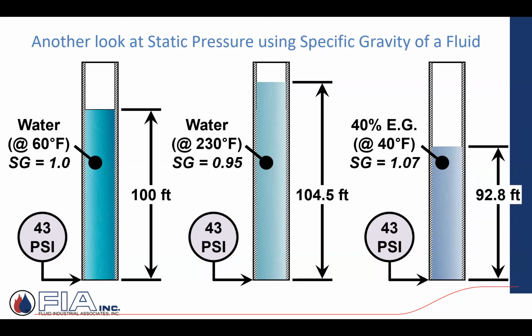Another look at static pressure: if I've got 60-degree water and I've got 100 feet, do the math, it's 43 PSI. That's what the gauge would read at the very bottom of that 100-foot column. If I had 230-degree water and I was reading 43 PSI, it would technically be 104.5 feet, because my specific gravity at 230 is slightly different than at 60 degrees, a little lighter. If I had ethylene glycol, a 40% mixture, that specific gravity is a little different, a little heavier. So now at 43 PSI, I'm only developing 92.8 feet of head. So specific gravity can influence.